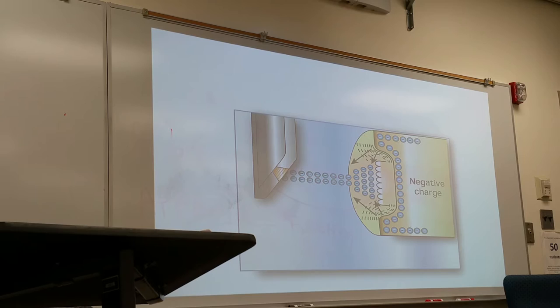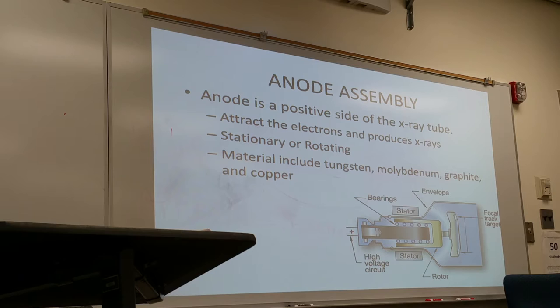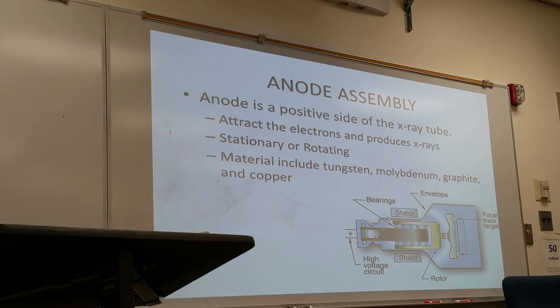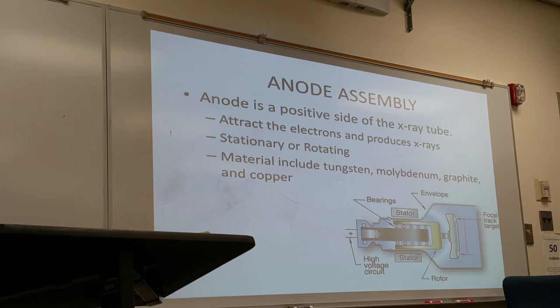The anode side is the positive side of the x-ray tube. It is mainly made up of a large tungsten disk, and this is where x-ray photons are produced — the source of x-rays. The anode attracts the incoming electrons from the cathode, and after their interaction with the tungsten disk, x-ray photons are produced.